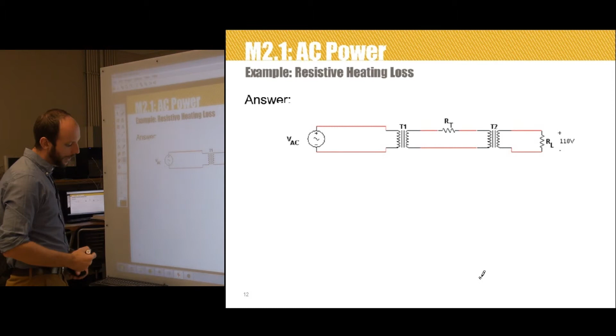In this case, VRT is just the current on the primary side of the step-down transformer, I(T2, left), times the resistance RT, which is 11 amps times 3.28 ohms. That gives you 36.08 volts. So the voltage here is 36.08 volts, the voltage drop across the transmission line.